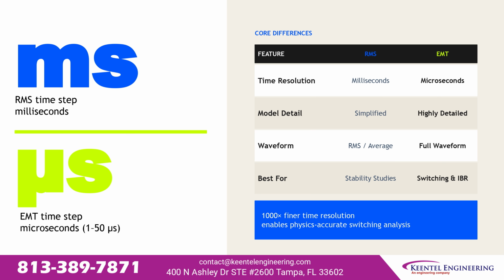The core difference between RMS and EMT comes down to time resolution, and that single factor changes everything downstream. RMS operates at millisecond time steps. EMT operates at 1 to 50 microseconds. That is 1,000 times finer resolution. In terms of model detail, RMS uses simplified average representations. EMT uses full physics-accurate models. In terms of waveform, RMS gives you the average. EMT gives you the full waveform: every switching event, every harmonic, every transient.